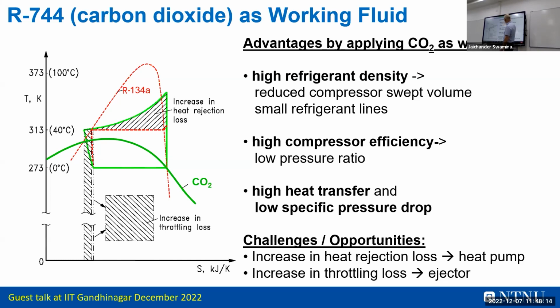The high refrigerant density is good. We can have a very small compressor and small lines, which is also good in industrial refrigeration. Imagine you have these huge capacity plants for freezing and so on, and you need insulation, and there is never space. But with a smaller pipe, you get sufficient insulation and the losses are minimum compared to a chiller system where you have to pump a glycol or so, which is huge, and the insulation. Pressure ratio is low, it's good. And we have very high heat transfer coefficient and low specific pressure drop, so the heat exchangers can be very well adjusted, very highly efficient. The challenges are as shown here, here and there. However, if you want to do heat pumping with CO2, that's why we have all this heat pump for hot water heating.